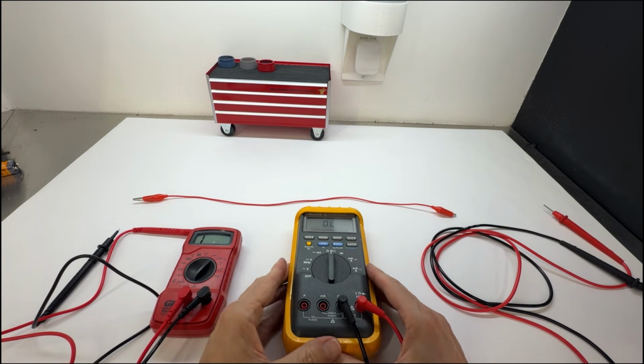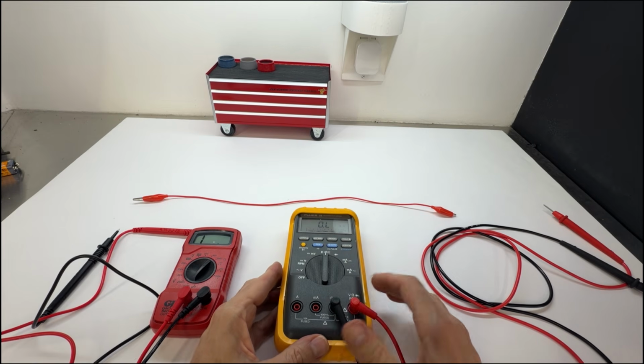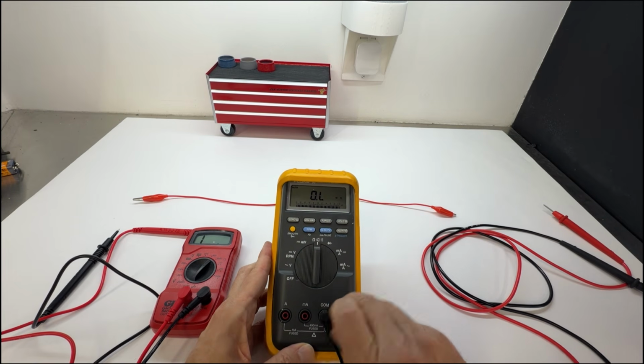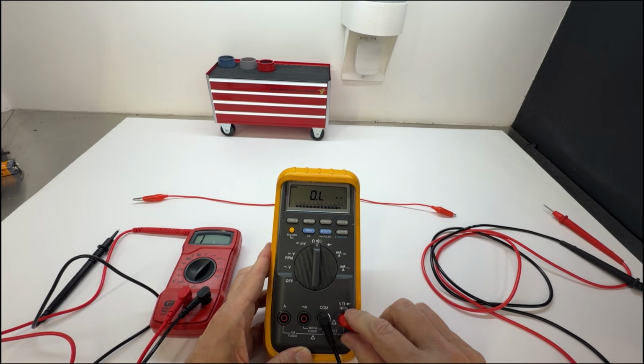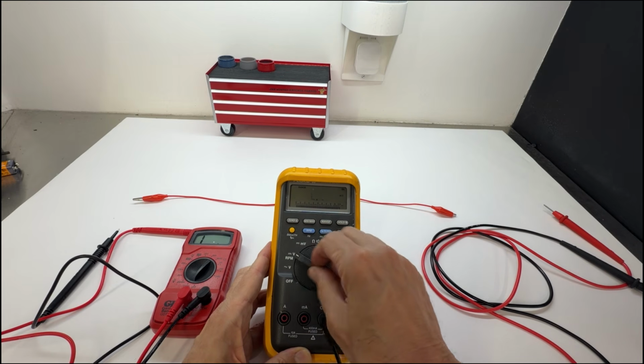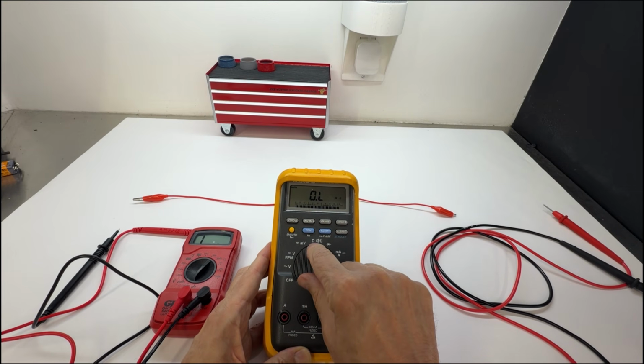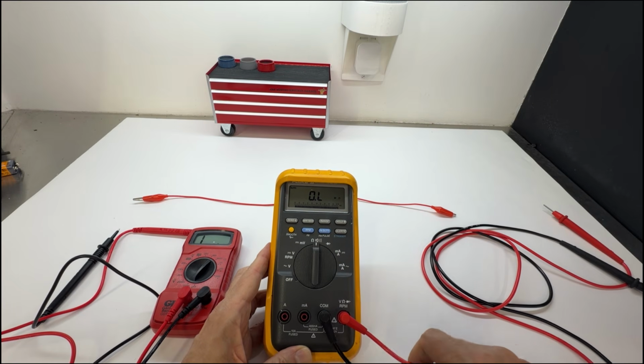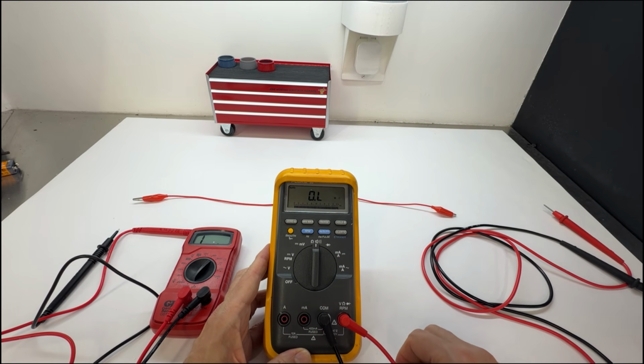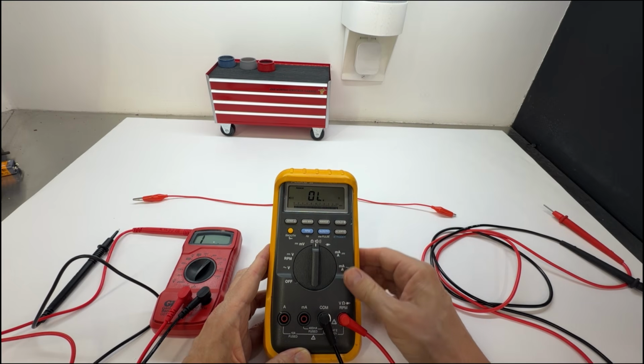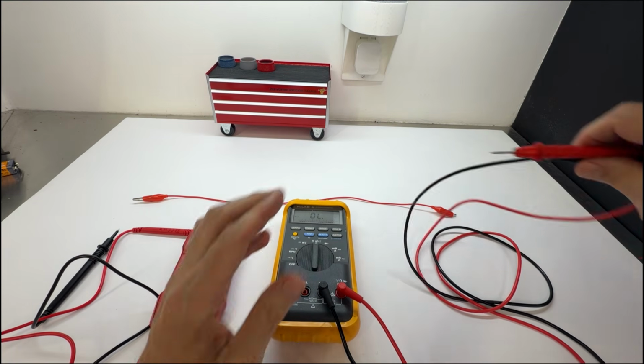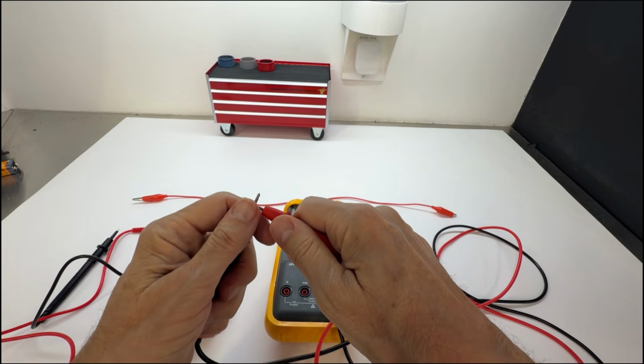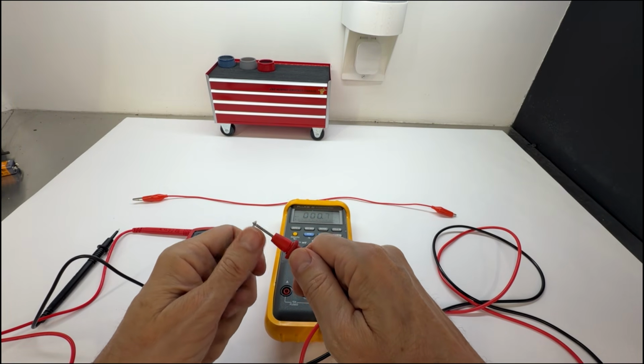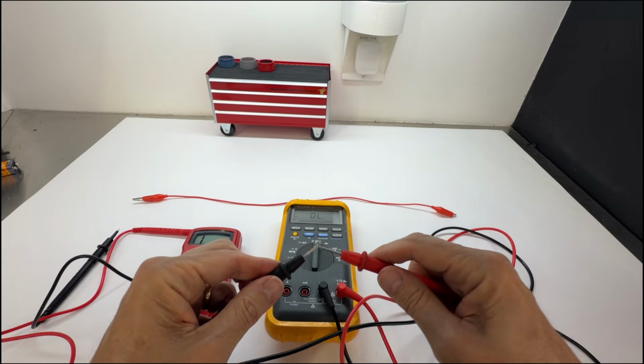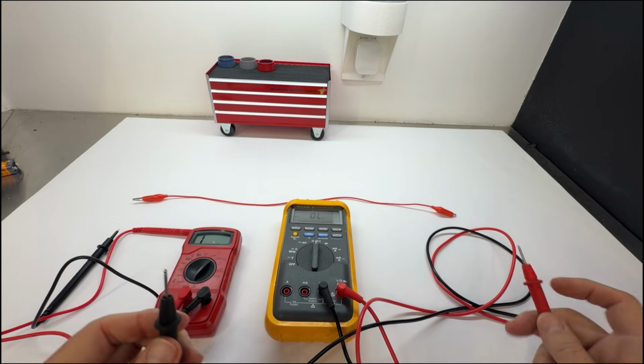If you have a higher end one like this with multiple ports, for continuity you just want to make sure you've got the red probe in the port that has that little omega sign, which is the sign for ohms. The dial needs to be set to the same omega sign. That's how you put this meter into the mode for checking resistance. This meter also has a little button, which is nice because it sounds a beeping sound whenever there's direct contact between the two leads.